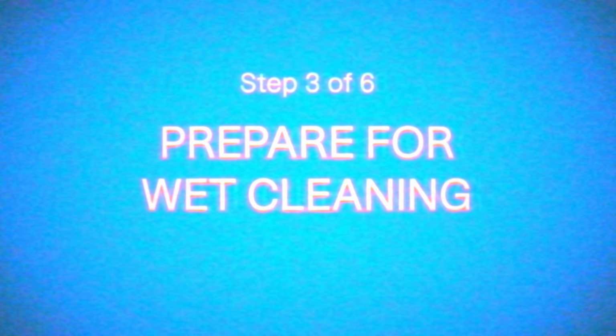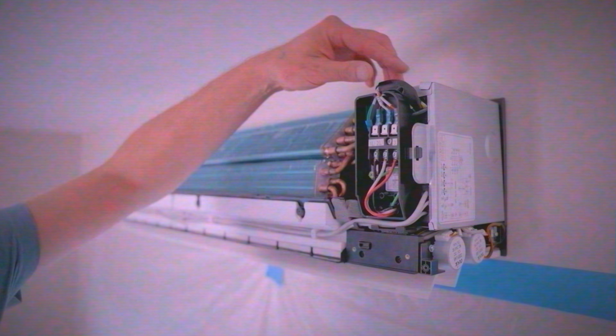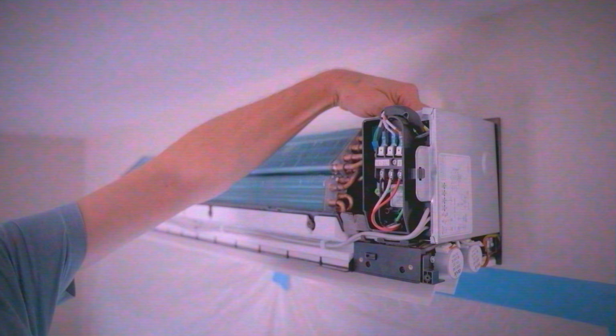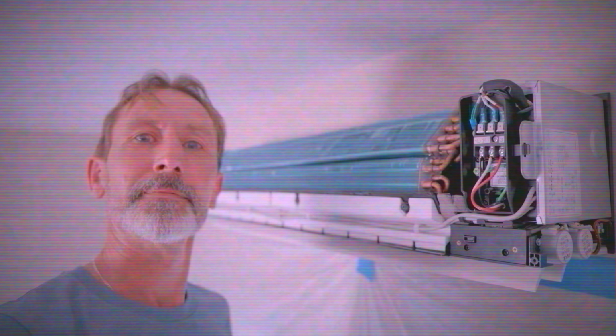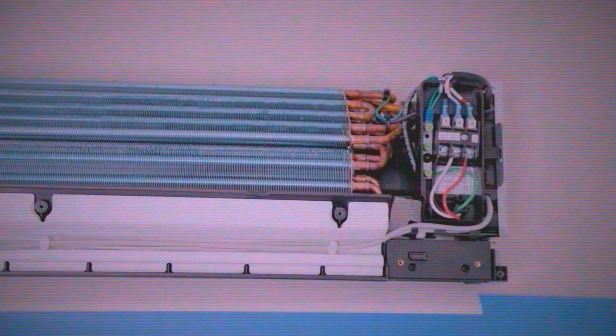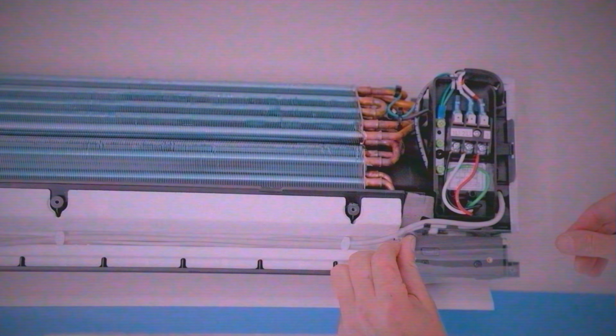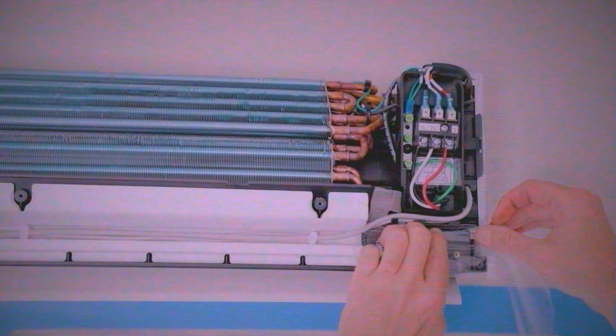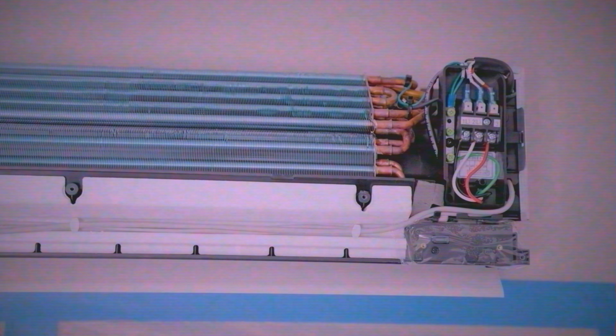To prepare for wet cleaning, first inspect and prepare the electrical terminals. Check all screws and tighten them if needed to ensure secure connections. Look for any corrosion, discoloration, or damaged insulation. If you spot any damaged components, replace them or contact the installation partner if replacements are not available. Next, cover the electrical components and seal vulnerable openings.